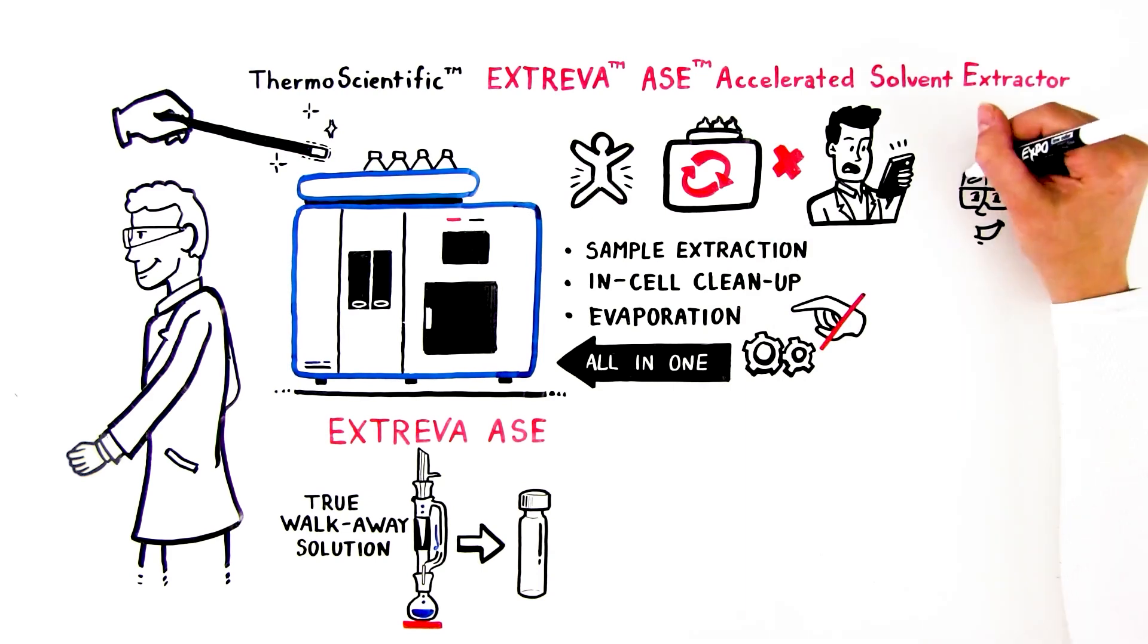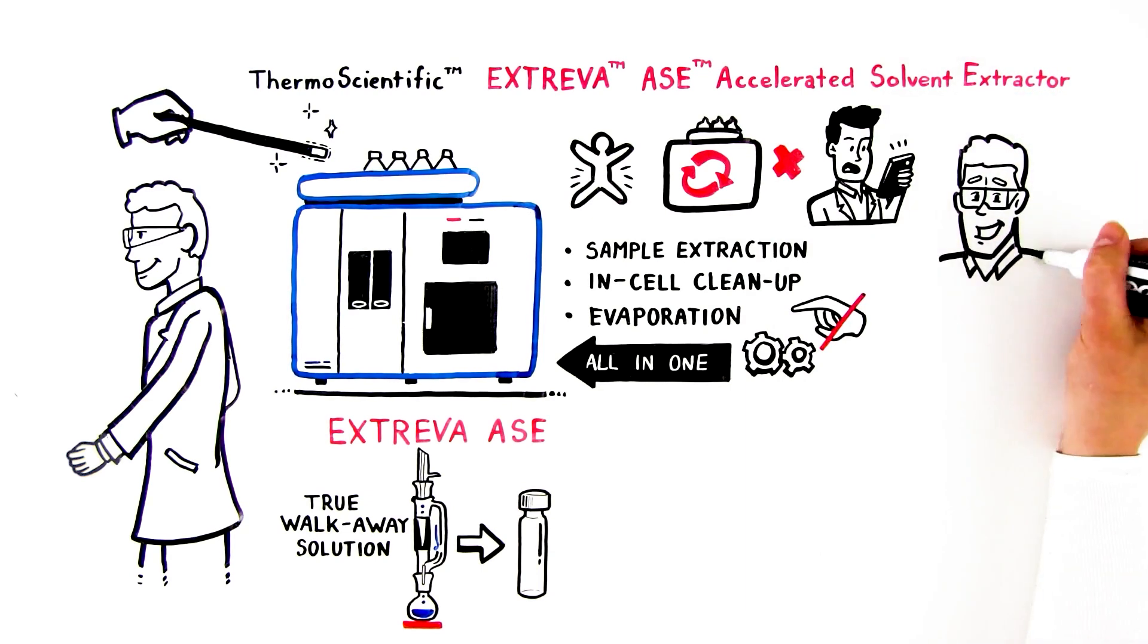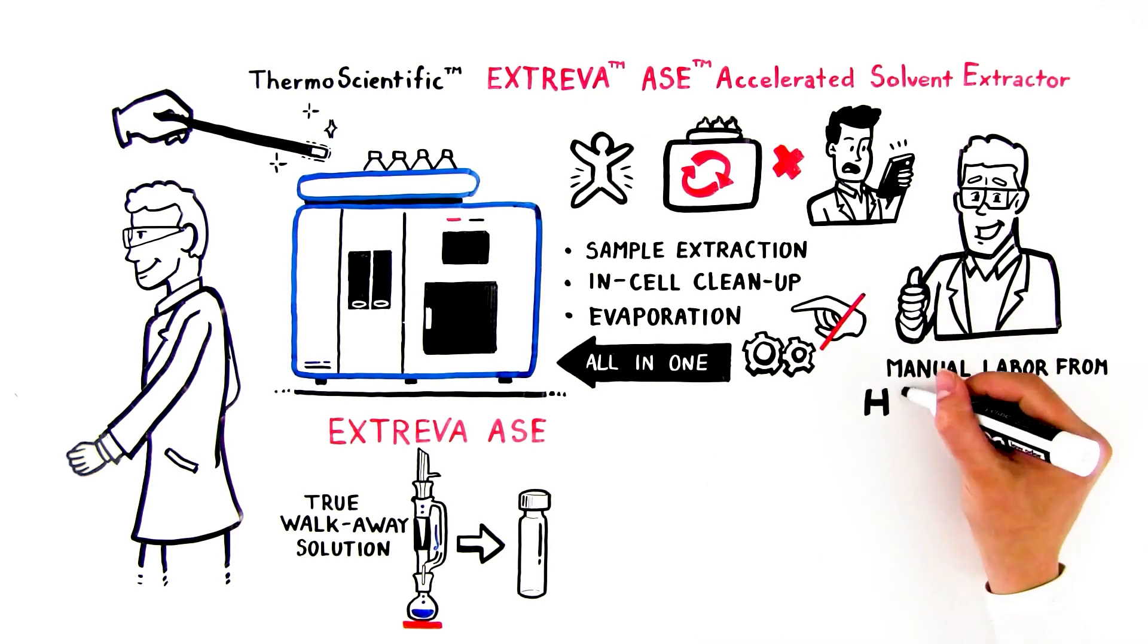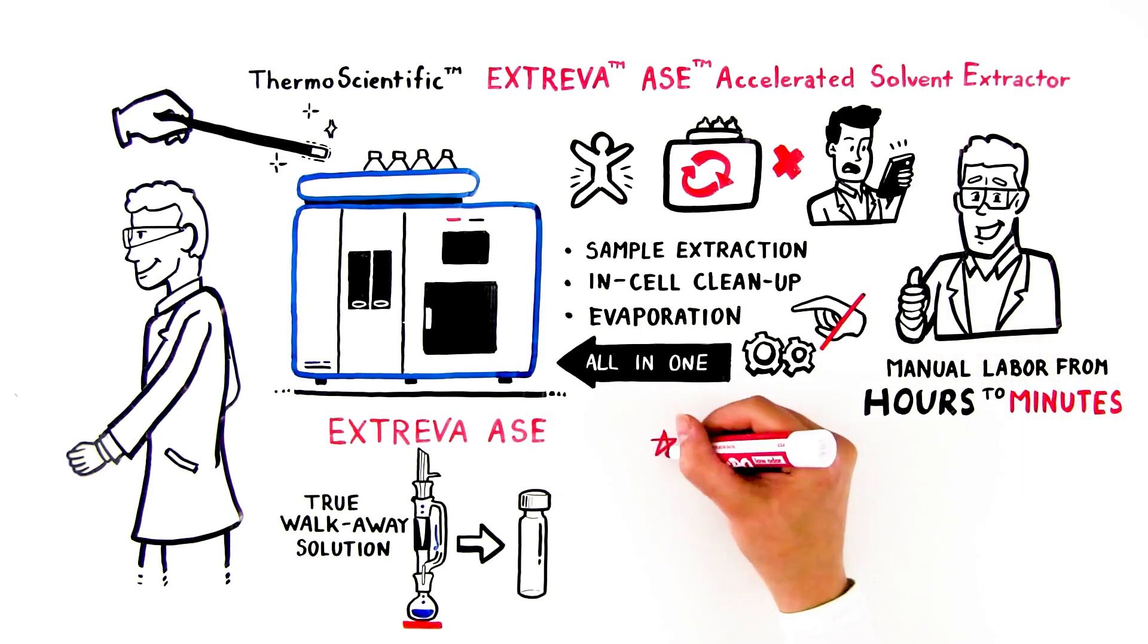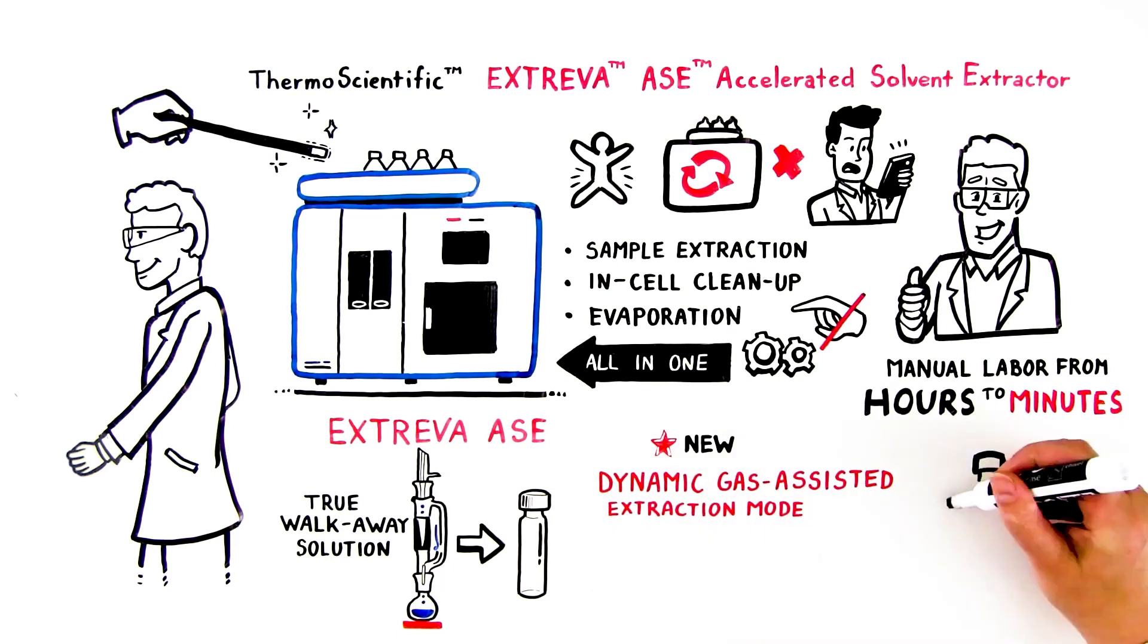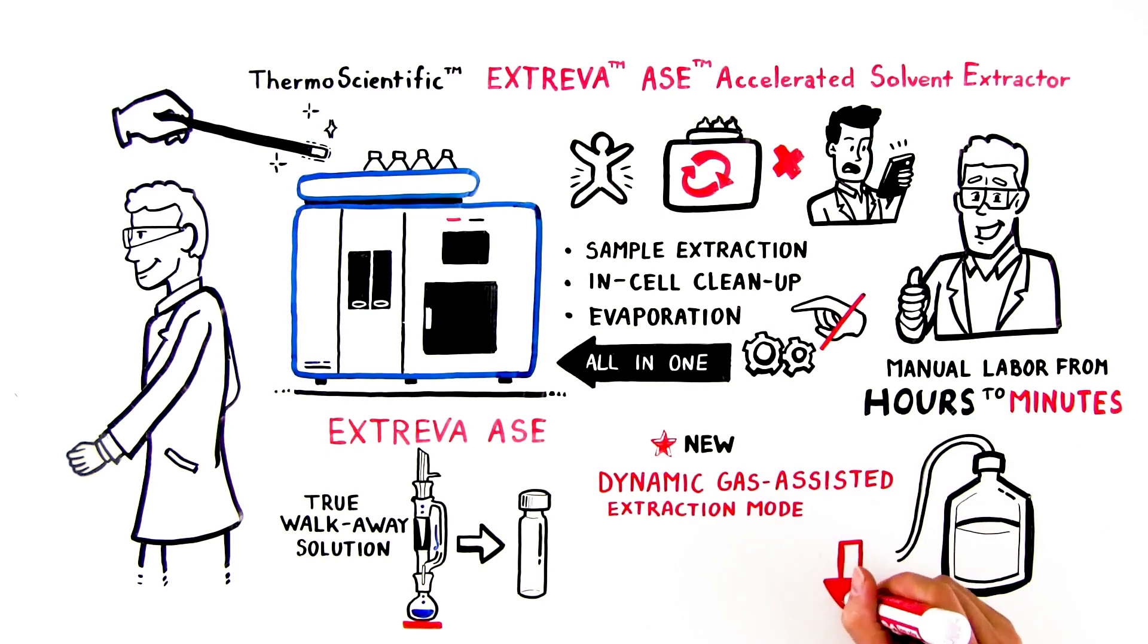That means user interaction is no longer necessary for each step, which cuts the manual labor required from hours to minutes. Using the new dynamic gas-assisted extraction mode, solvent consumption is also greatly reduced, down to between 5 and 100 milliliters per sample in most cases.